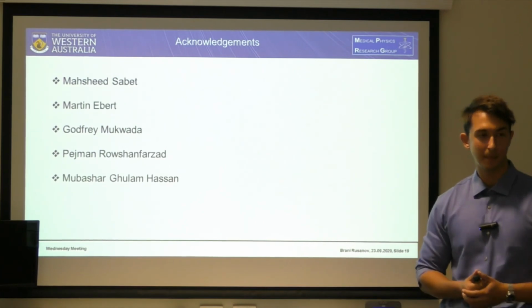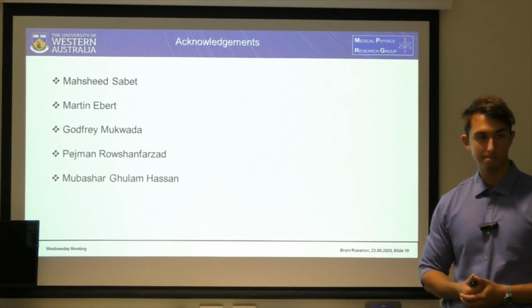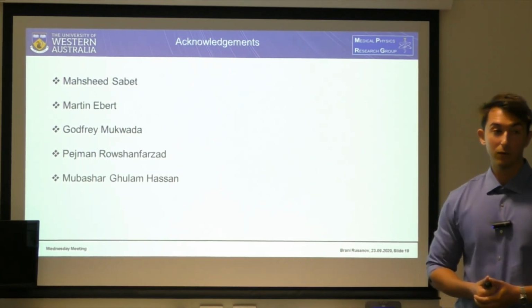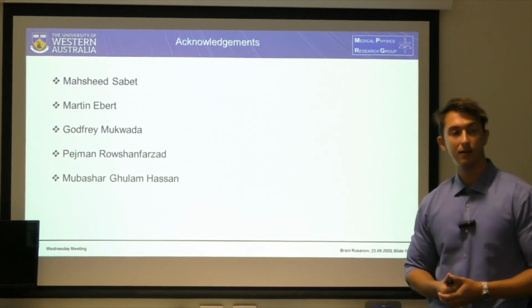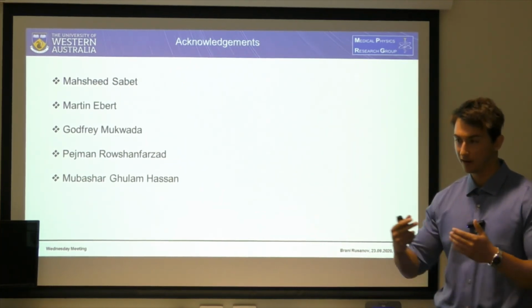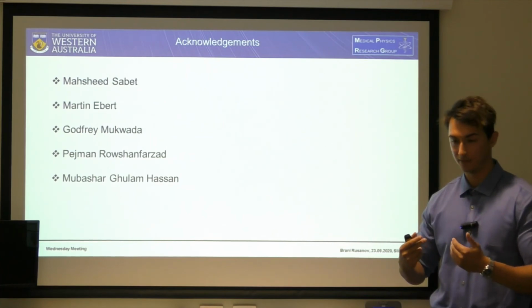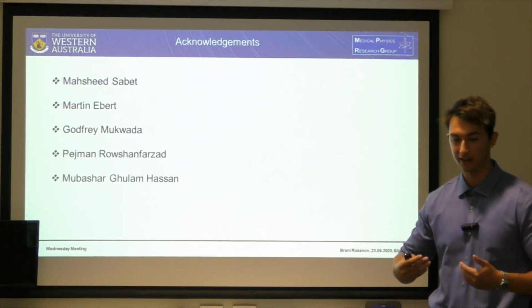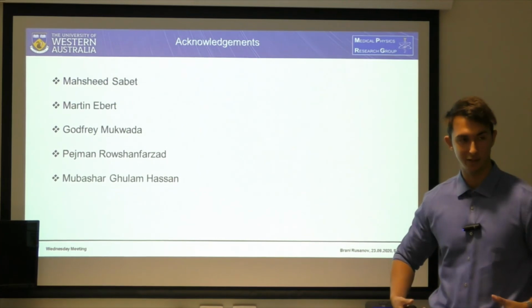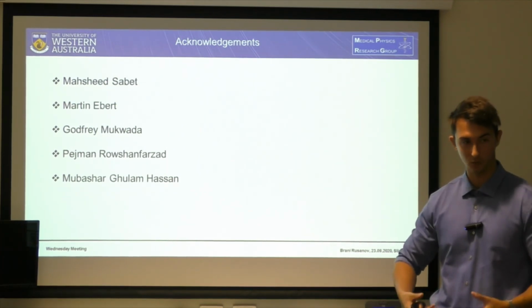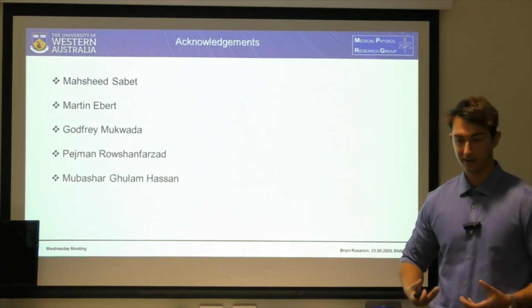I just want to add a note to that. How dependent is that on the anatomical area, like a head or a large pelvis, small pelvis? Interestingly enough, I investigated the head for this particular case. I would have to retrain it. Obviously, for pelvic scans, you use more mAs because there's more anatomy there, and so it had to be retrained.